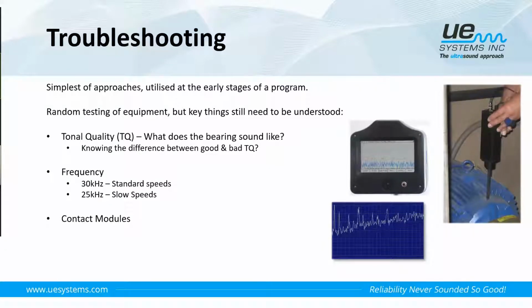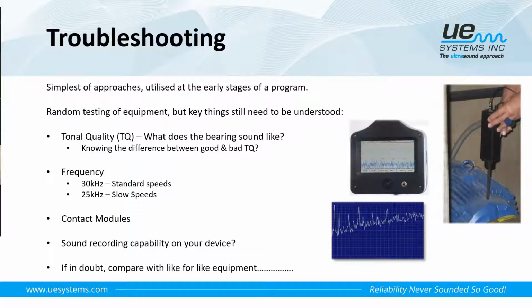We're using our contact approach with our modules. And if we have the ability to perform a sound recording on our device, then that may aid us as well, because as we are troubleshooting, you might want to get a second opinion from your colleagues. If you have the ability to sound record, you can play that back on the software, and you can then have a peer review on what your thoughts are with this. And if in doubt still after this, then you can move on to maybe comparing it with a like-for-like asset on your site, which will bring us on shortly to our next methodology. But first of all, I want to give a couple of examples that we have had when we have done some simple troubleshooting on some assets.